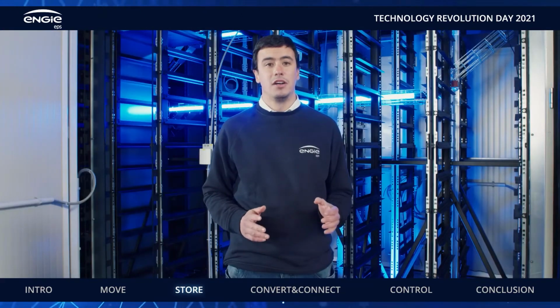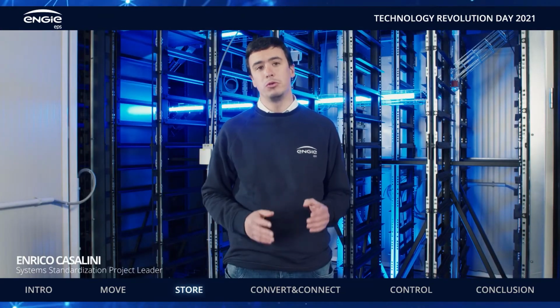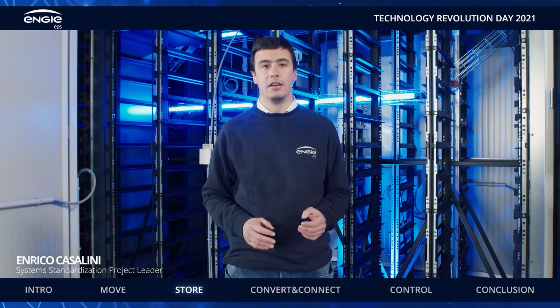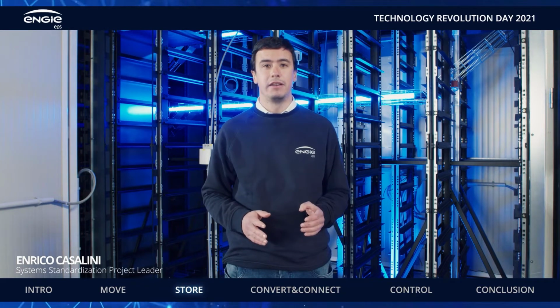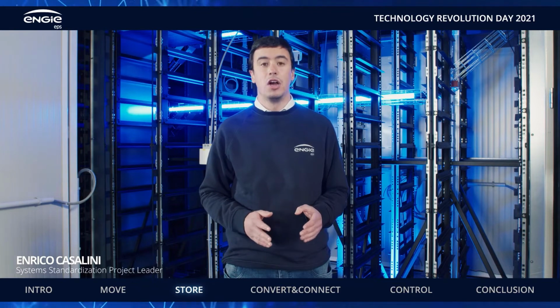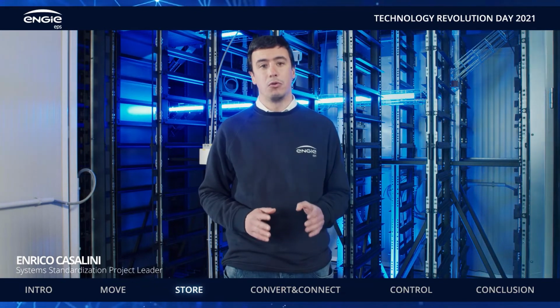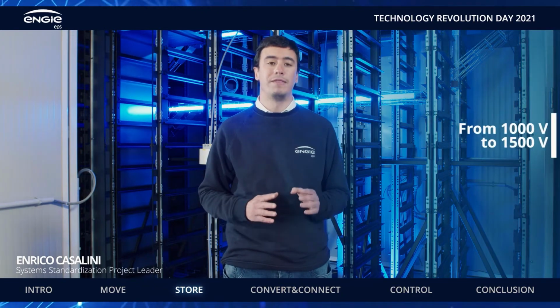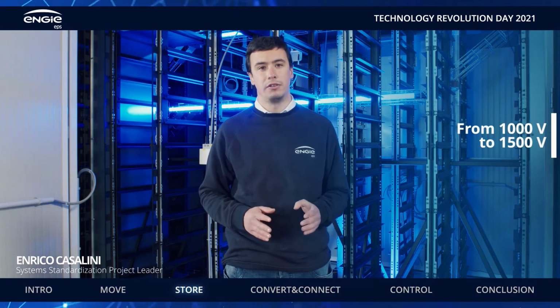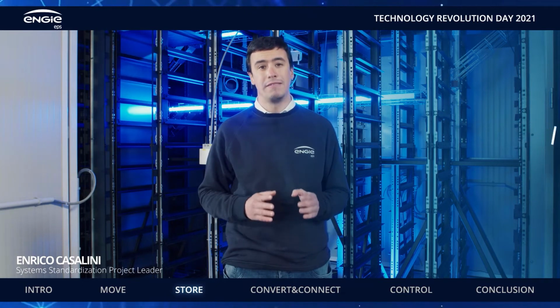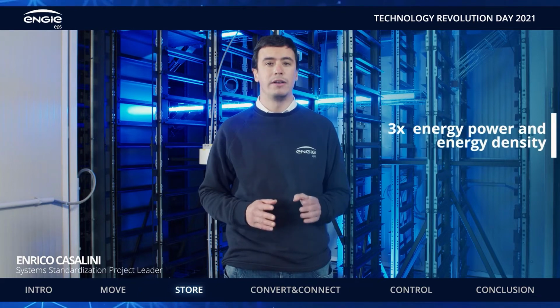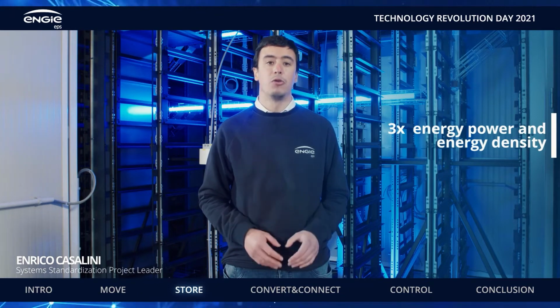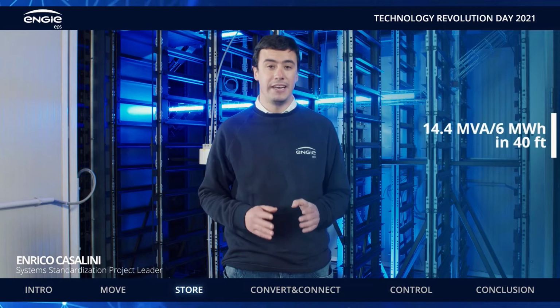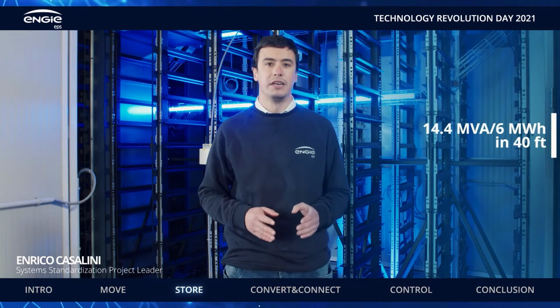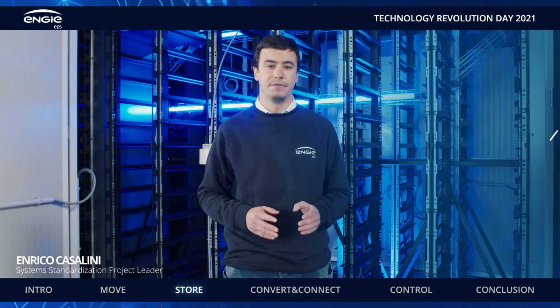Here at EPS, we have an obsession for continuous improvement in technical design. Our highest HD container family is the result of this drive. We have developed this new family, raising the DC bus voltage level from 1000 to 1500 volts, and increasing by more than 3 times the power and energy density of our solutions, reaching up to 14.4 MVA of power conversion systems and 6 MWh of batteries in a 40 foot ISO container.